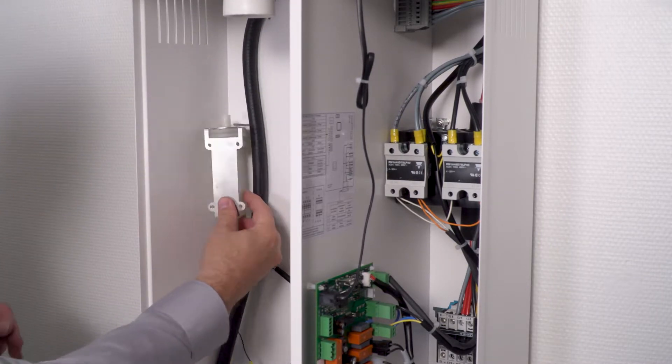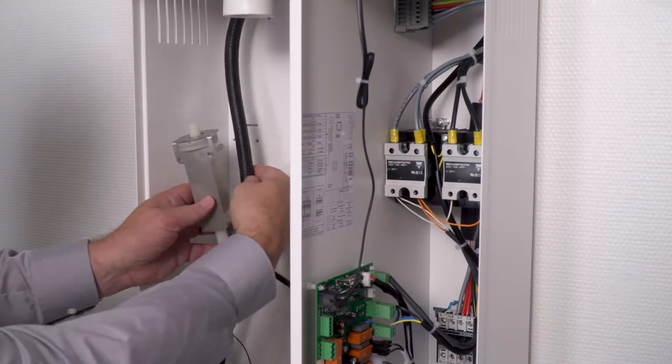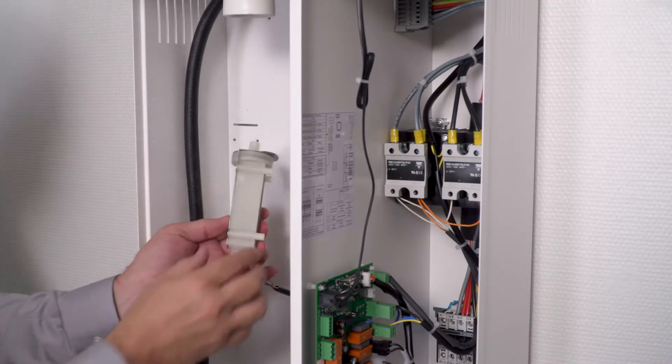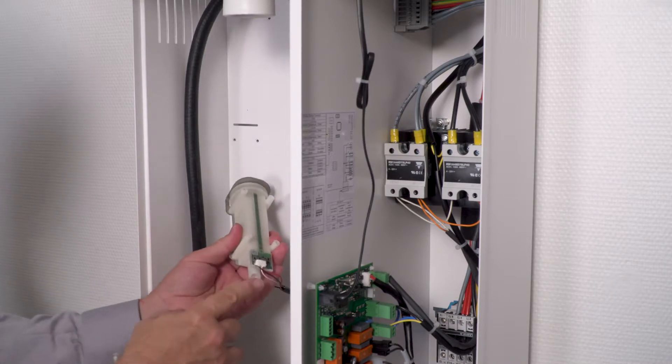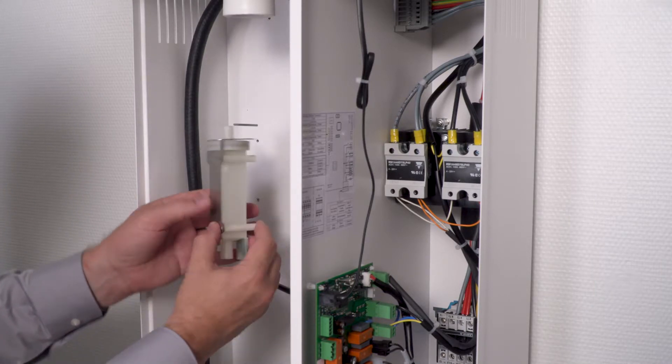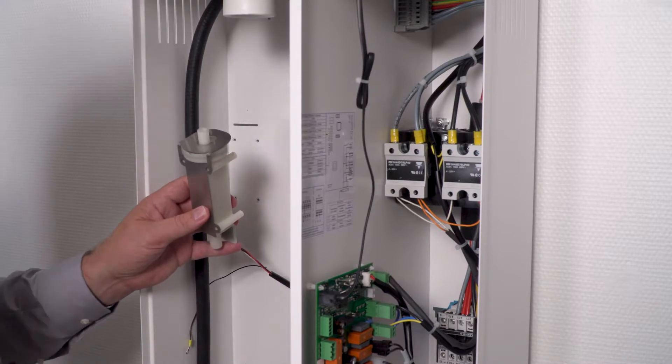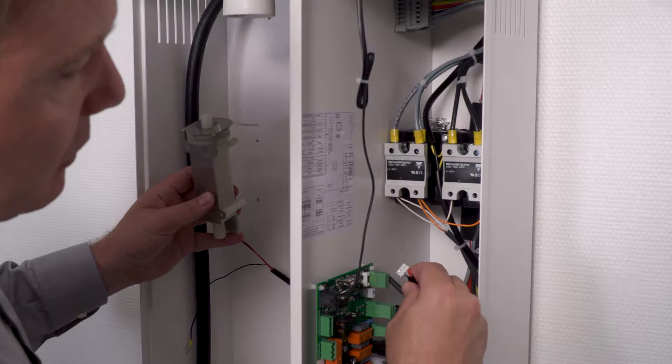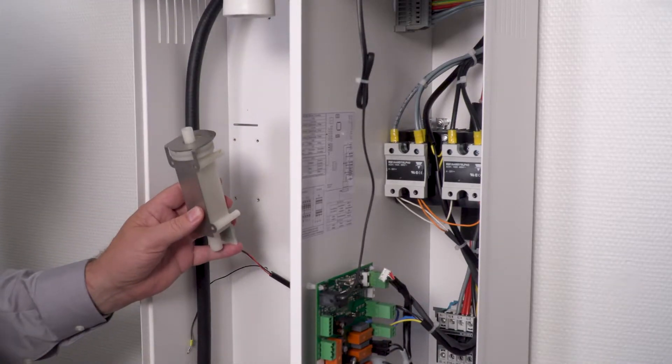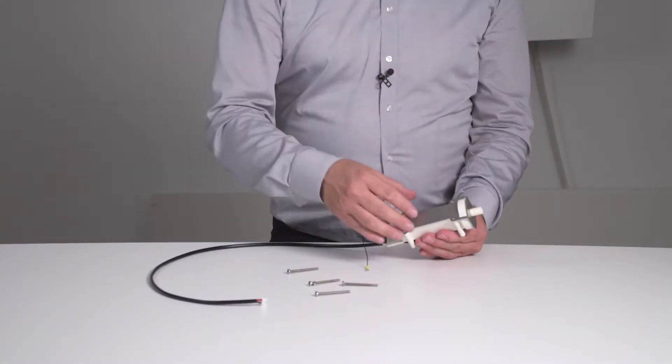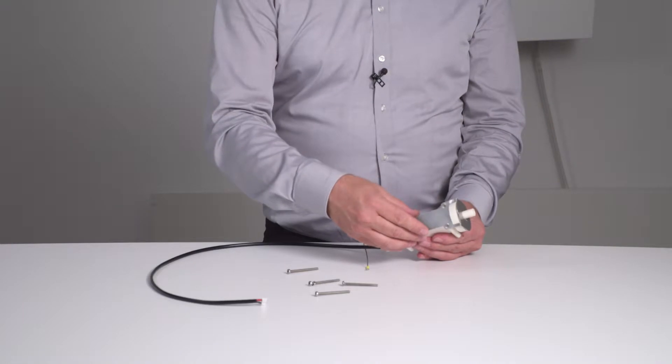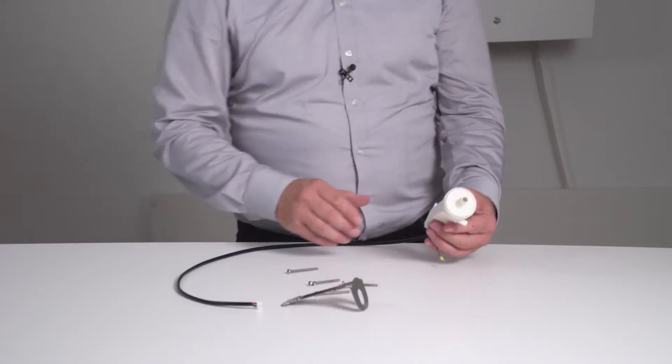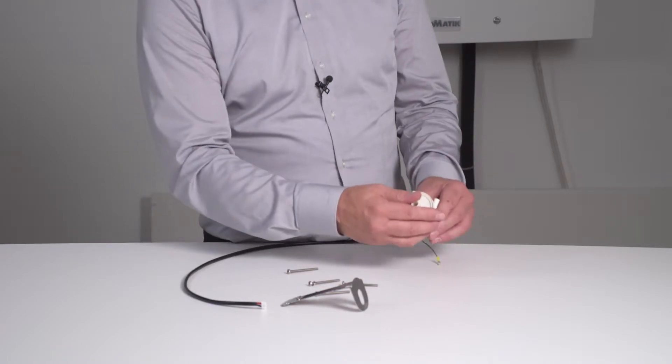Now I can remove the water level control from the back wall of the unit. It's important not to remove the contact plug directly from the water level control. Instead, remove the plug from the main board up here and pull it out of the unit. I now have the water level control in my hand. Now I can remove the shielding plate and open the tank of the water level control.